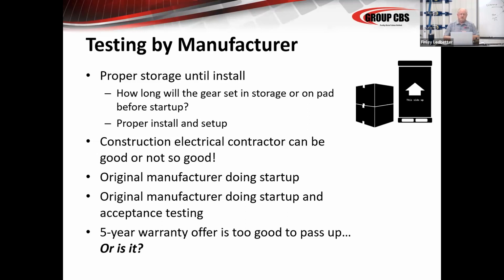So electrical contractors can be very familiar with this type of gear, or they can be first-time installers. And you see that quite often. So ascertain the level of expertise of your contractor, and that'll give you some idea how much time you need to stay hand in hand right there beside him. Is the original manufacturer doing startup? Is the original manufacturer doing startup and acceptance testing? So we're seeing more and more of that, especially in the data center world, where the original manufacturer comes in and convinces the user to allow them to do not only the startup, but the acceptance testing.